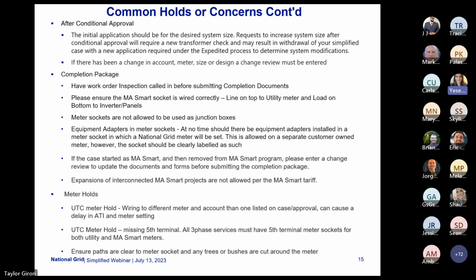Please ensure that Mass Smart is wired correctly. The line is on top to the utility meter, while the load is on the bottom to the inverters and panels. Many times we see that the Mass Smart is wired upside down, and that Mass Smart isn't counting the generation correctly on the solar for that customer.